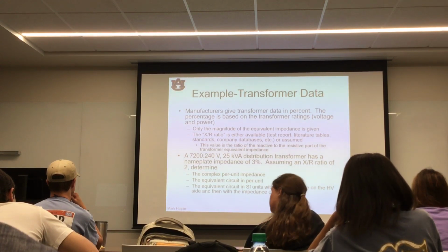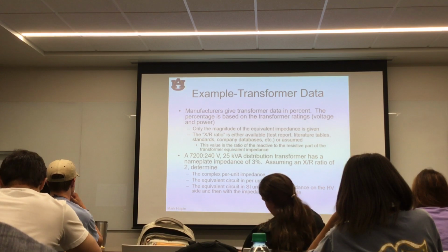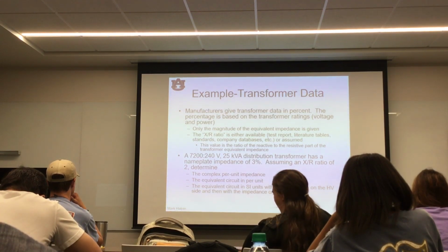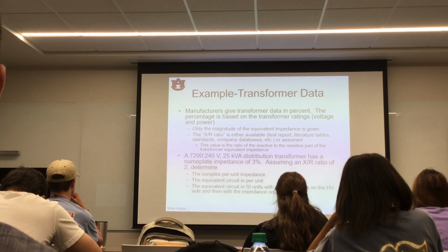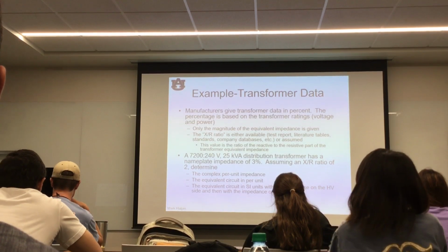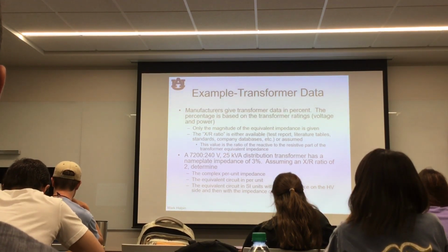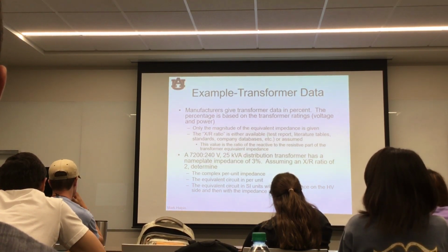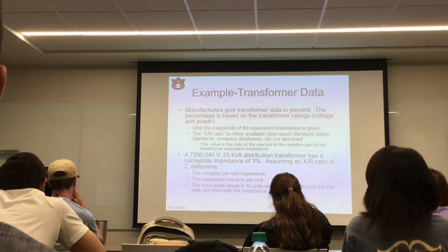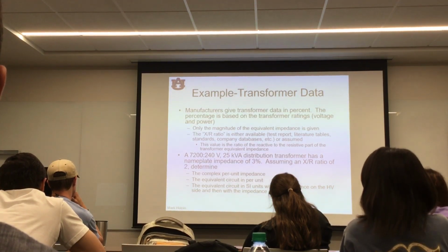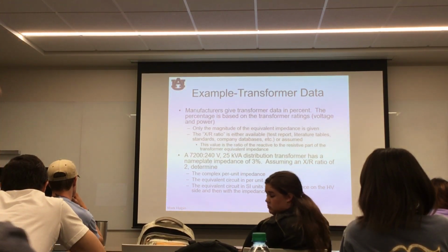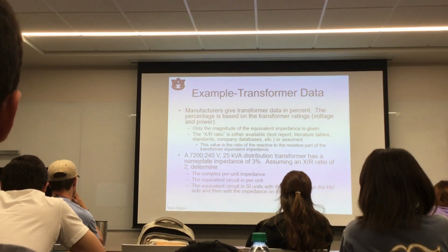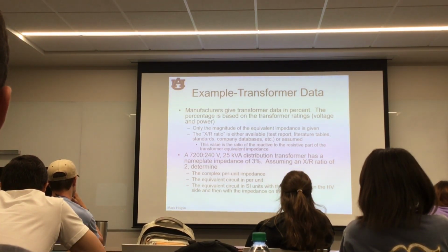A big company like Alabama Power, Georgia Power, that buys hundreds or thousands of these things, well, when those purchase acquisitions are sent to the vendor, in this case Howard Industries, in the purchase order will be something where Howard Industries has to give typical impedance information. Not impedance information for any specific one, but typical. And utility companies save that, okay? So we might have historical information.